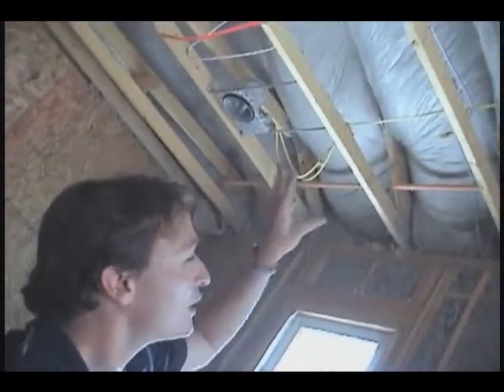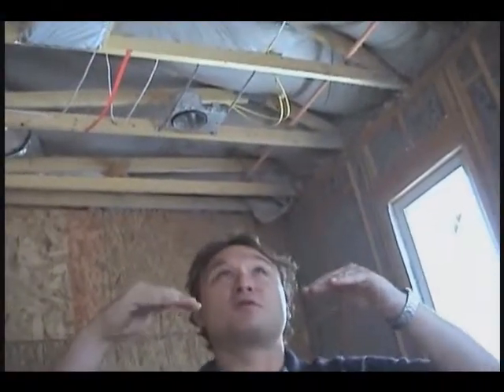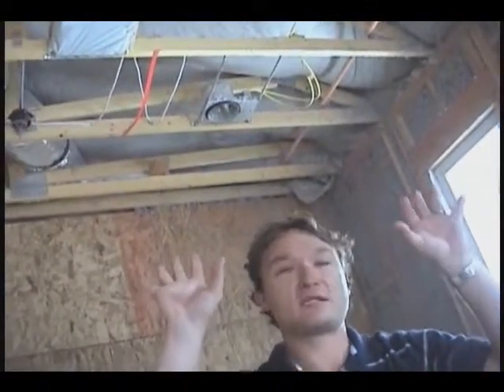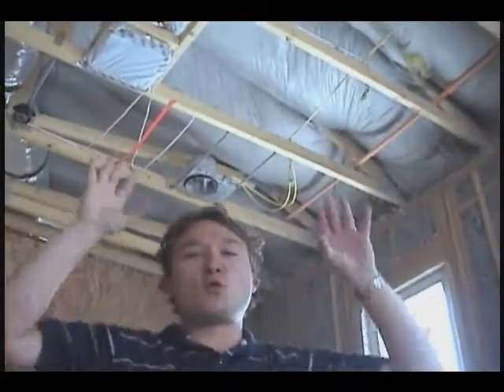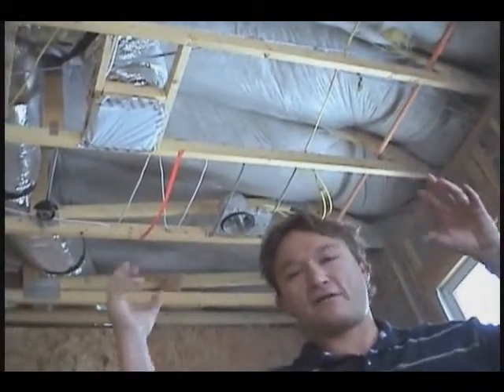Another thing we did with the blown-in insulation is we actually applied it in these large pillows that you kind of see up in the attic. Now, one thing that's a little bit different in this type of house, instead of putting the insulation directly on top of the drywall, which we've done over the years in Las Vegas, we're actually now putting the insulation on the underside of the roof sheathing. What that does is it allows us to create a climate-controlled attic. Therefore, we do not have a very hot attic environment. So what we're doing here is we're basically expanding the heating and cooling envelope of the house, and we're not looking at it as 2 different systems. We're looking at it as one system in its entirety.